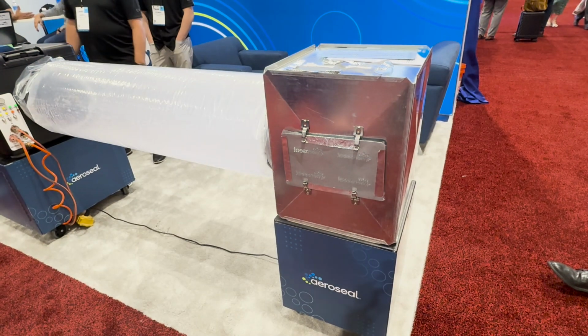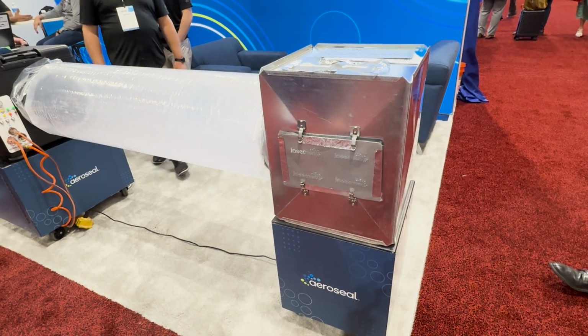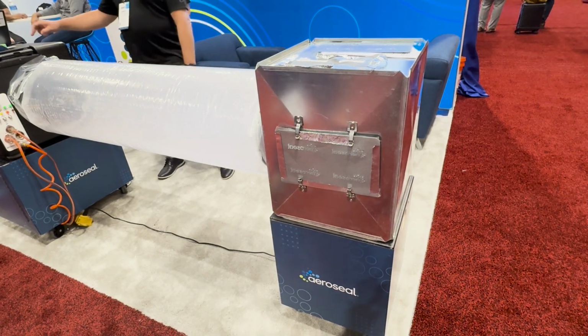And so how does Aeroseal technology address that issue? Instead of doing it externally, Aeroseal uses a whole different methodology. It seals the ductwork from the inside out. The process works by blocking the ductwork off from the ends, taking air, pumping it into the ductwork, and forcing that air to leak out the holes. Then we take a sealant, an atomized vinyl polymer, and push it into the ductwork, forcing it to leak out. As it leaks out, it seals from the inside out.